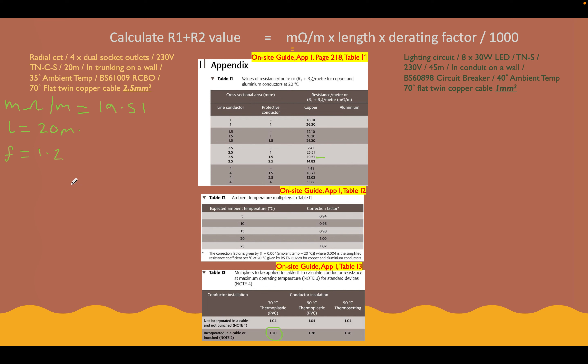So let's put this into the calculation. Our R1+R2 for this circuit is equal to our de-rating factor multiplied by our length multiplied by our milliohms per metre value, all divided by 1,000. That's 19.51 × 20 × 1.2 ÷ 1,000, which gives us a value of 0.46 ohms. So we've got our R1+R2 value for the radial circuit. Let's do our lighting circuit exactly the same way.